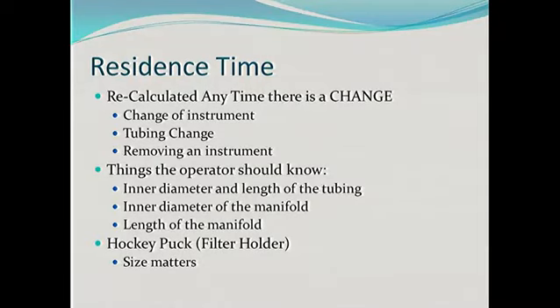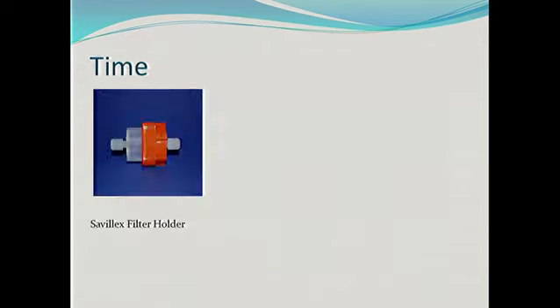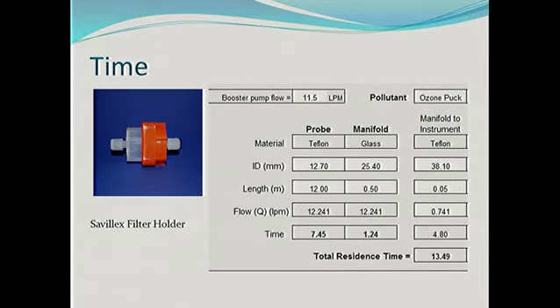Okay, we talked a little bit about residence time. It's calculated anytime there's a change, tubing change, removing of an instrument. Remember to know the inner diameters of the stuff that you're dealing with, the length. Hockey puck size matters. We talked about that, and here's a little bit of an example. In this case, we show that this is with an API instrument, so it changed it by 4.8 seconds, just the hockey puck size. So just be careful when you have these lower flow instruments. You got to do some makeup to get through that hockey puck. But 13 seconds, they meet the requirement.